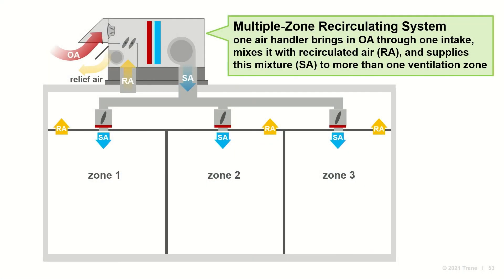In a multiple zone recirculating system, one air handler serves the ventilation needs of more than one zone. After outdoor air enters through the intake, it mixes with recirculated air from the zones before being conditioned and delivered back to those zones. The most common example is a conventional multiple zone VAV system using a package rooftop unit, floor-by-floor self-contained unit, or an air handling unit.